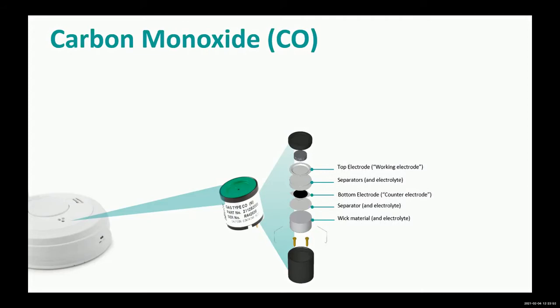If it dries out, the unit will go into fault. And also if it gets overexposed to moisture, it will go into fault as well. So it's very important that it retains a certain moisture level within the unit itself. And underneath that is where we get the expense on the sensor, because we have to use platinum and gold, and that's where a lot of the expense comes from. So it's a fairly intricate device, and it works very differently from any smoke detector.